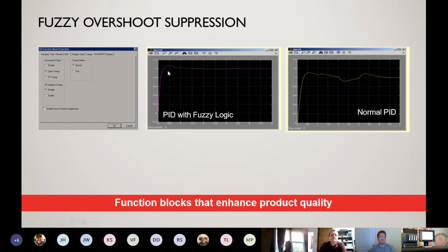This is just a description of fuzzy logic. Again, fuzzy logic, when we talked about it in the UDC world, is something that operates separate from your PID, proportional band, integral and derivative. But what it's there for is to minimize overshoot and undershoot of your process control at set point. So on the left-hand side is a PID with fuzzy logic. On the right-hand side might be stereotypical of a normal PID without fuzzy logic.